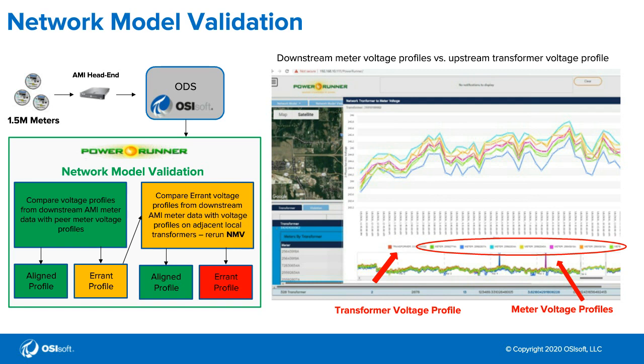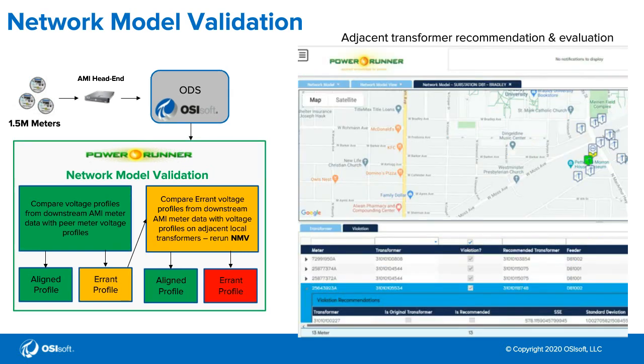We then run this through a comparison to determine the best adjacent transformer to reassign this meter to. We use a geofence, in this case 0.1 kilometers, or 100 meters away from the original transformer assigned to the meter. Then we evaluate all the voltage profiles for the surrounding meters to come up with the best fit on a recommended meter or transformer.